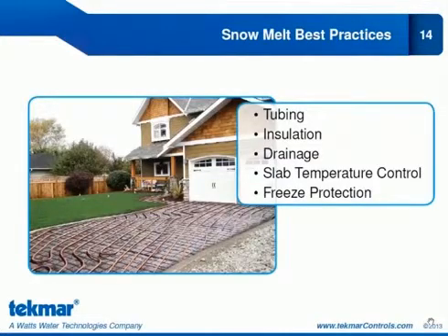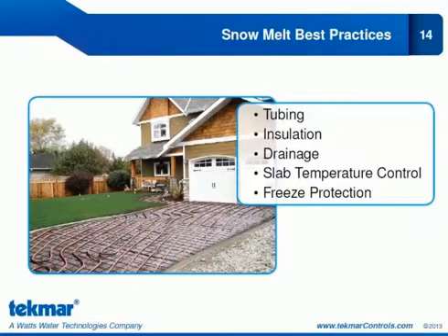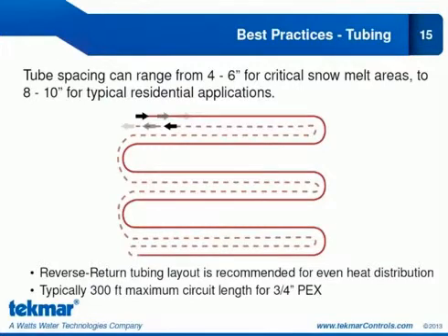We'll look at some of the best practices associated with snow melting, covering tubing, insulation, drainage, slab temperature control, and freeze protection. For tubing, tube spacing can range from 4 to 6 inches for critical snow melt areas, to 8 to 10 inches for typical residential applications. A reverse return layout is recommended for even heat distribution. The typical maximum circuit length for 3/4 inch PEX is 300 feet — it's not advised to exceed this.